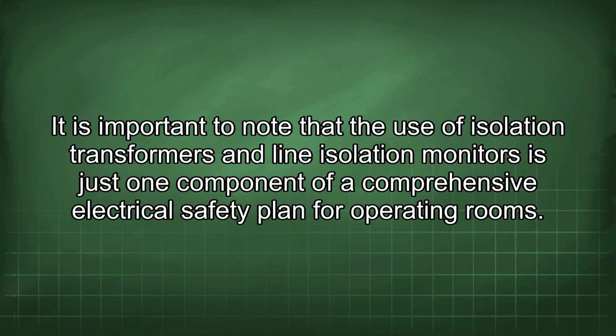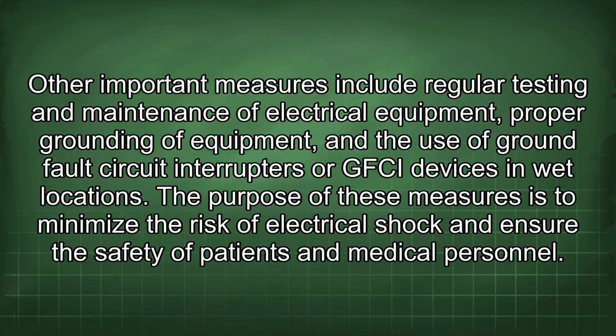It is important to note that the use of isolation transformers and line isolation monitors is just one component of a comprehensive electrical safety plan for operating rooms. Other important measures include regular testing and maintenance of electrical equipment, proper grounding of equipment, and the use of ground fault circuit interrupters or GFCI devices in wet locations. The purpose of these measures is to minimize the risk of electrical shock and ensure the safety of patients and medical personnel.